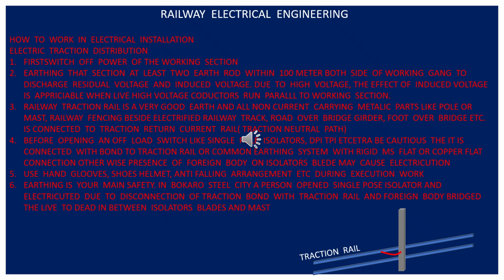But what happened in Bokaro? The fellow went to open the isolator. He had not checked the bond, this structure bond, and opened it. A foreign body, a steel string, was present on the movable blade, and when he opened it, the live end touched the dead end. Dead end means the earth end. The mast was energized, and he was electrocuted because the bond was disconnected from the traction rail. So be careful. This is the system of working in the traction distribution system.